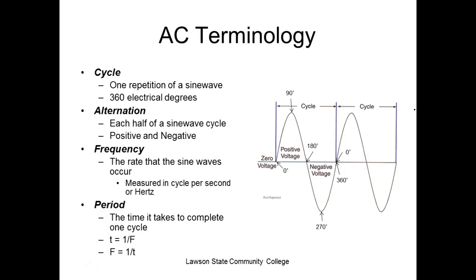With AC, we don't get a direct reading, we get this effective voltage. You've got to be extremely careful with your meter in an AC circuit. If you measure 0, you need to verify that it's set on AC, because if you've got it on DC, it's going to measure 0. That's because when you put it on DC, it gives you the average, it doesn't give you the effective voltage.